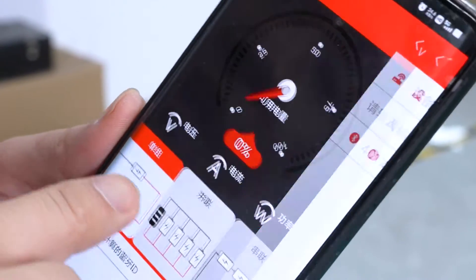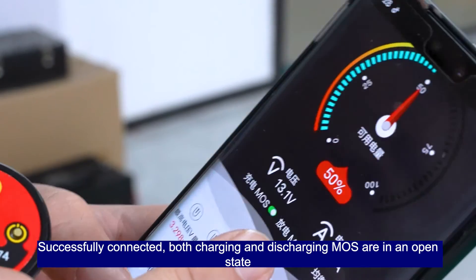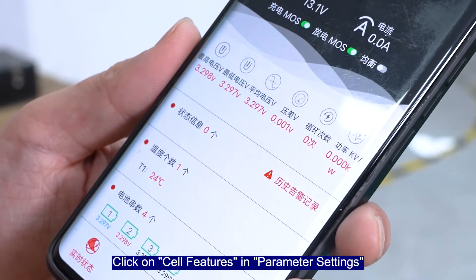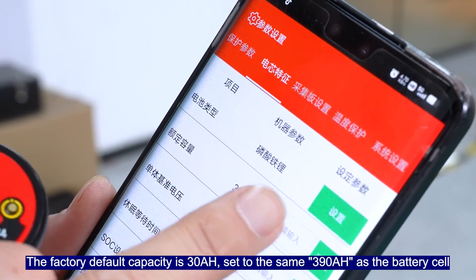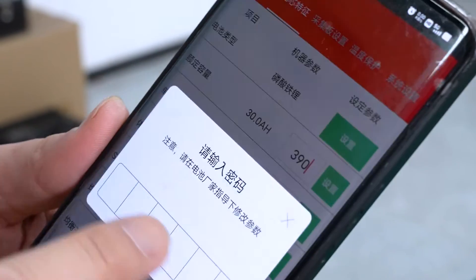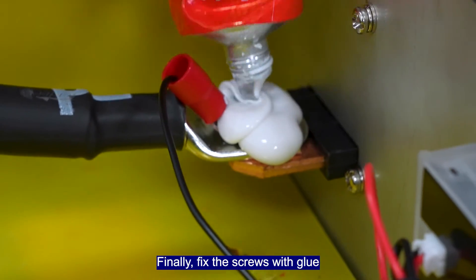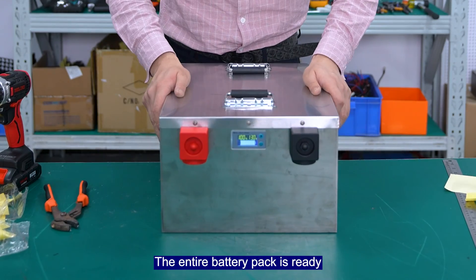Connect Bluetooth. Successfully connected — both charging and discharging MOS are in an open state. Click on cell characteristics in parameter settings. The default capacity is 30 ampere-hours; set it to the same 390 ampere-hours as the battery cell. Finally, fix the screws with the grill. The entire battery pack is ready.